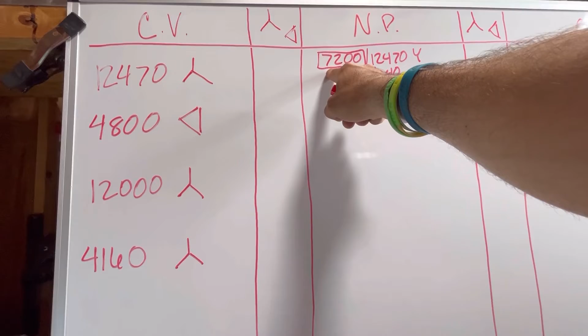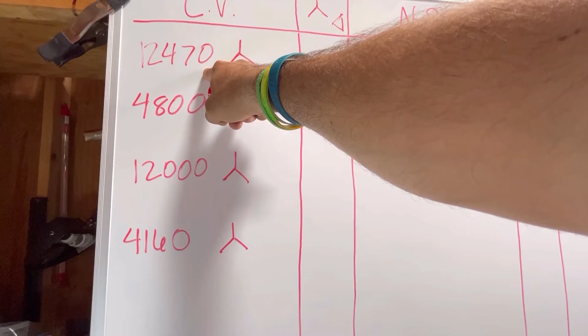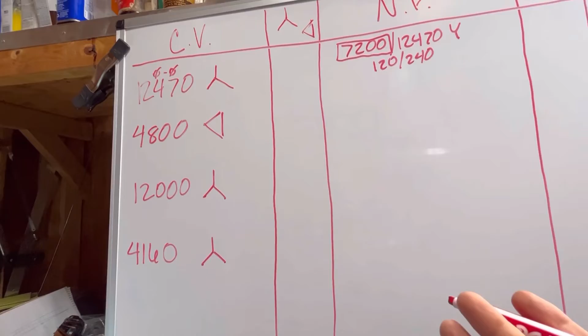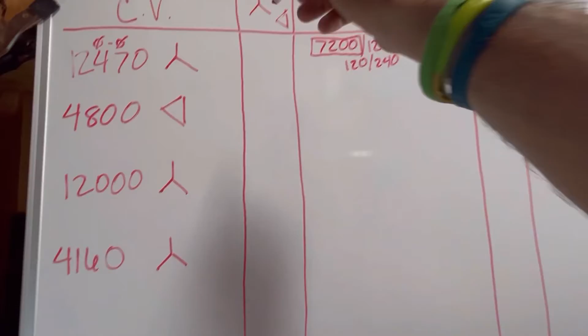And here's a quick, easy little hack, okay? What you need to do is ask yourself, where does 7200 volts live on this circuit? Is it phase to phase or phase to neutral? We know that 12470 is the phase to phase potential, right? Because that's how we name our circuit: phase to phase potential, type of circuit. So in a 12470 circuit, 7200 volts lives phase to neutral, right? Phase to neutral is going to be a Y hookup.